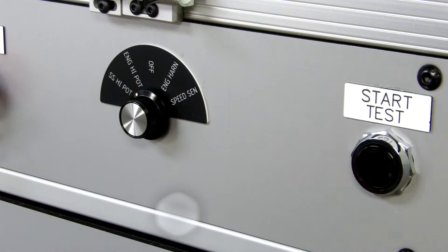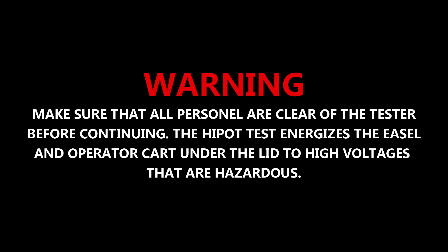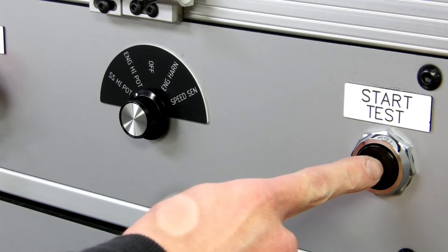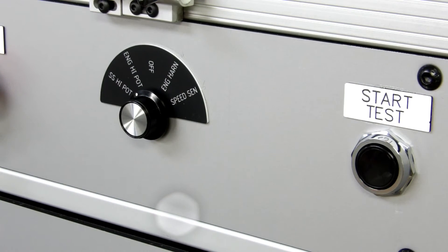Back at the operator console, change the selector switch to ENG high pot. This will change the software to the high pot screen warning. Make sure that all personnel are clear of the tester before continuing. The high pot test energizes the easel and operator cart under the lid to high voltages that are hazardous. Press the start button beside the selector switch to start the high pot test.